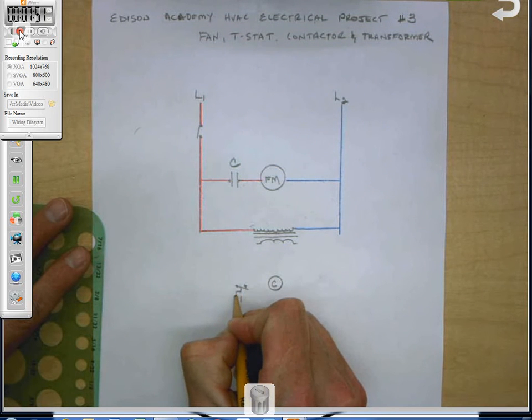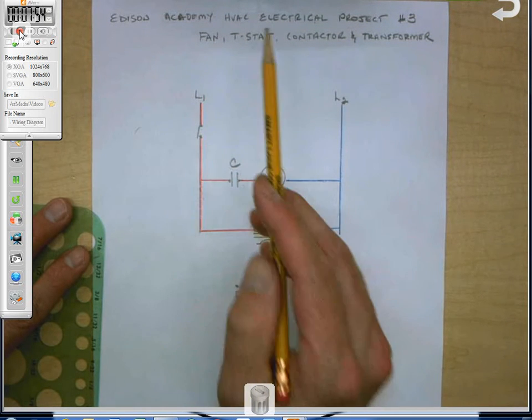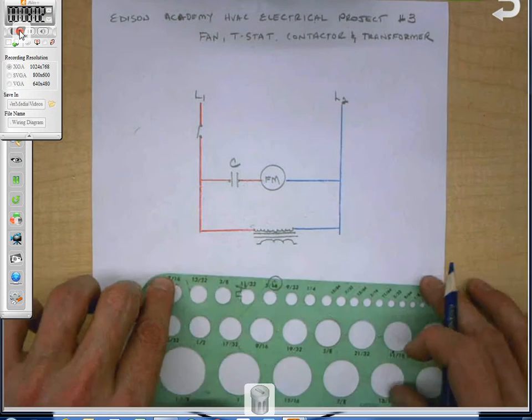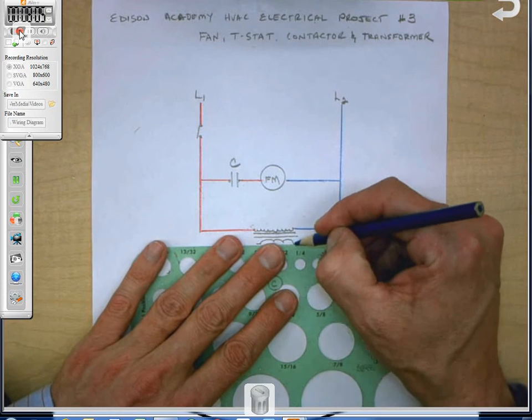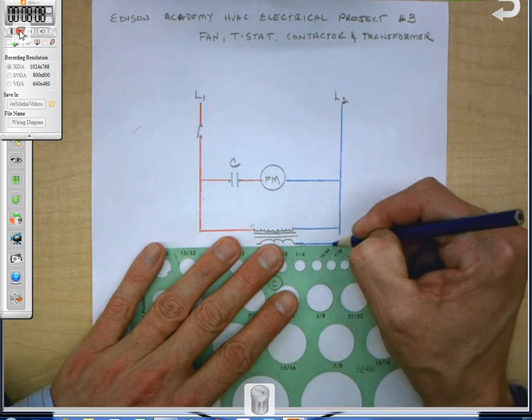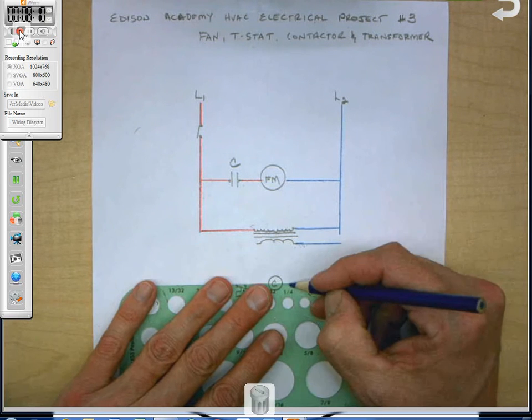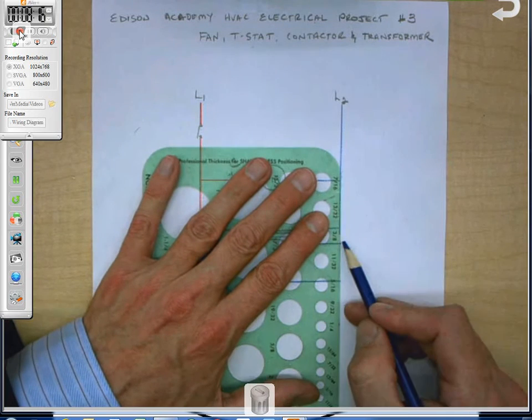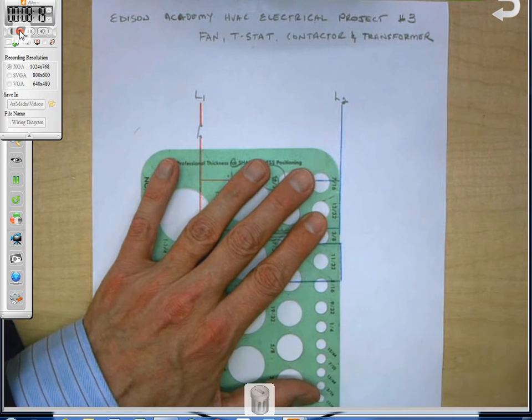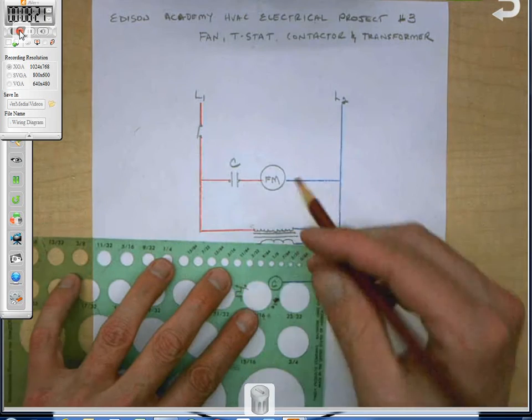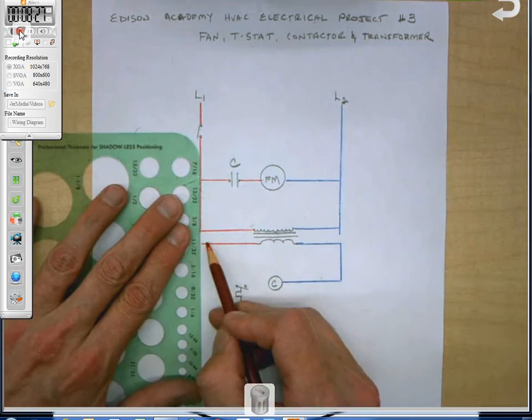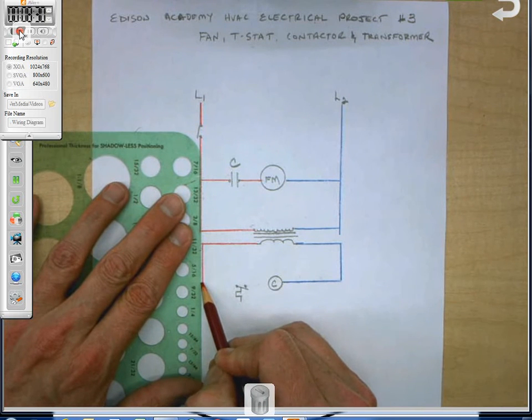So now I'm going to go ahead and put in the coil for the contactor. Now that's going to be controlled not with 120 or 240 volts, but with... I'm going to go ahead and use the 3/8 hole here. That's going to be controlled with 24 volts. So I'm going to put a little circle there. I'm going to put a C there. And what was controlling that coil? What did you have to wrap around Frosty for it to get power to that coil? So I'm going to draw this one below the screw. Because this thing closed on temperature rise. What was the piece right here that I'm drawing? Yeah, but what kind of switch that closes with temperature? What do they call it? Yeah, thermostat. You got it. Alright. So that's it. That's the loads right there and the control.